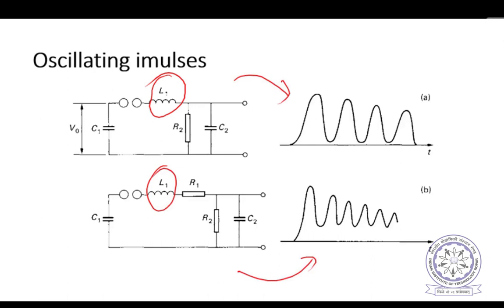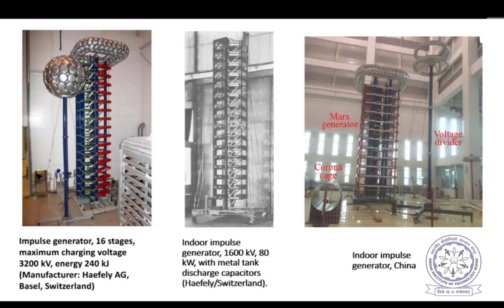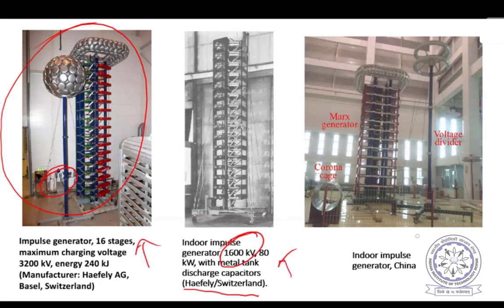These are the typical impulse generators. You can see this is 3200 kilovolts in Switzerland, made by Haefely. Very huge height. You can see the height of a human being here. Human beings are normally kept in high voltage photographs in order to compare the size, how big the equipment is. Similarly, this is 1600 kilovolts by the same company. This is an old circuit and this is the latest. And this is another circuit from a Chinese company. We also have a small impulse voltage generator, around 440 kilovolts, at IIT Ropar.